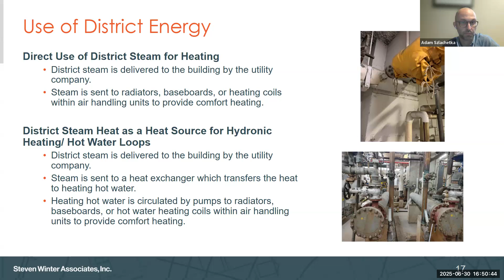That same steam that comes in on a pipe can also be used for hot water loops. So instead of steam traveling the pipes to the building, you have a process where there's a heat exchanger that does just what it sounds like. Steam heats up water. That water is what's circulated throughout the building to serve baseboard units or hot water coils, whatever system is pulling heat off of that hot water loop to heat the building. So the only difference is steam comes in, they just heat up water using that steam and pump it around the building as opposed to sending steam directly through the pipes inside.